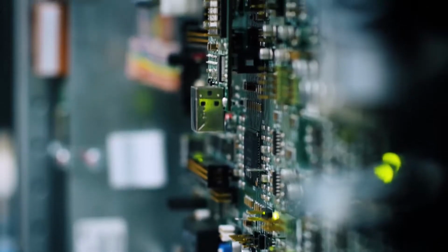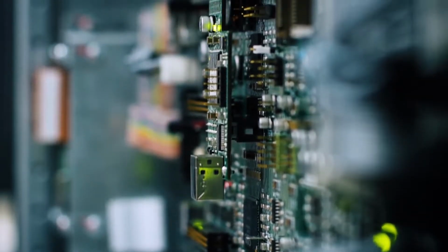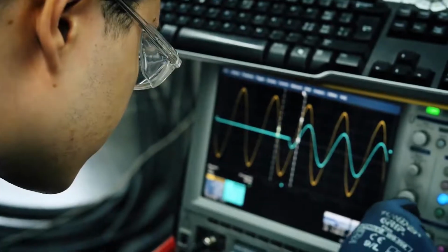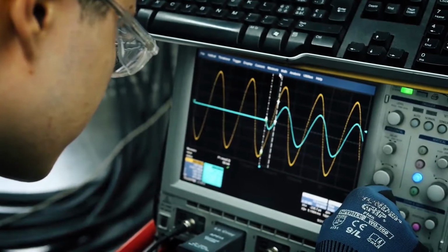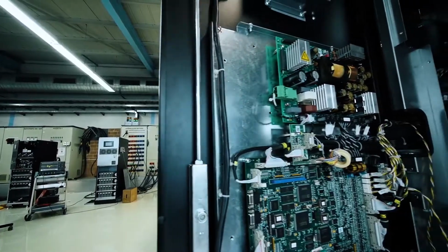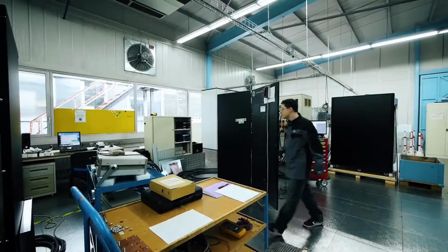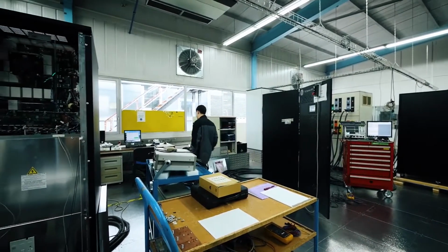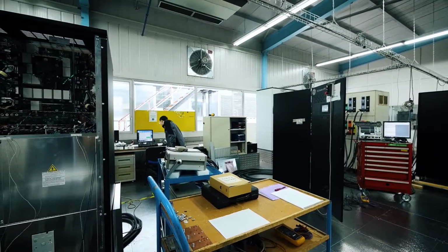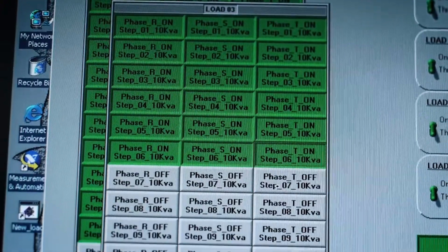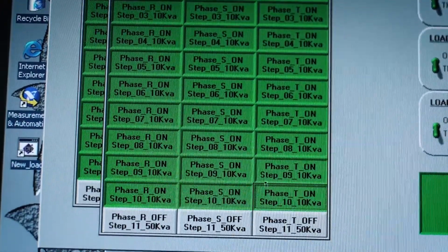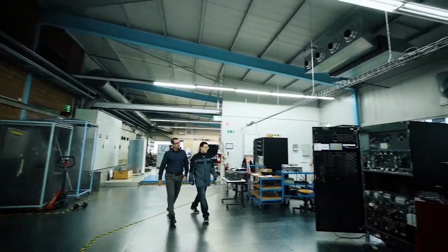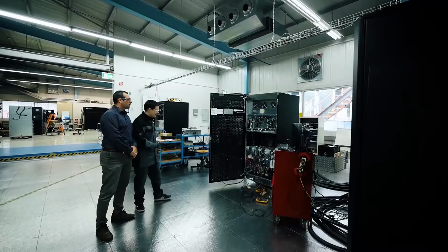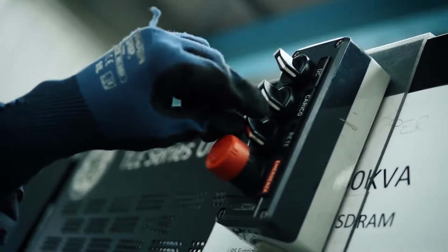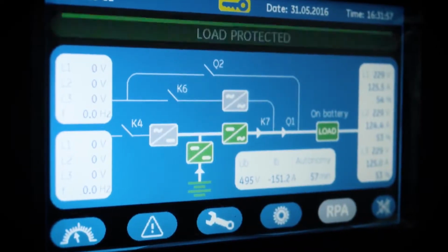It's worth mentioning the test is fully automatic. With the help of a computer, different events that may happen in the field are simulated. This stage lasts from 25 minutes to 4 hours, depending on the UPS model. One of GE Production's advantages is a customer acceptance test, which can be carried out in the customer's presence.